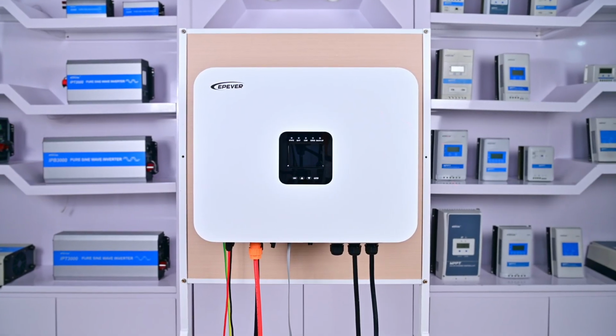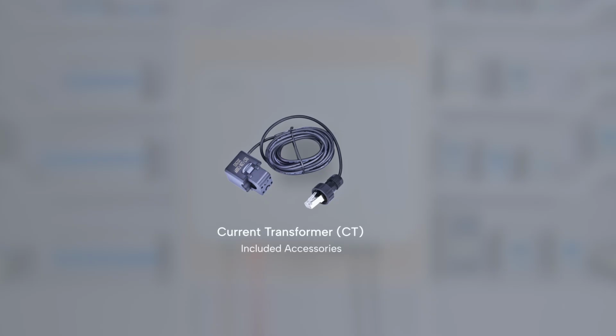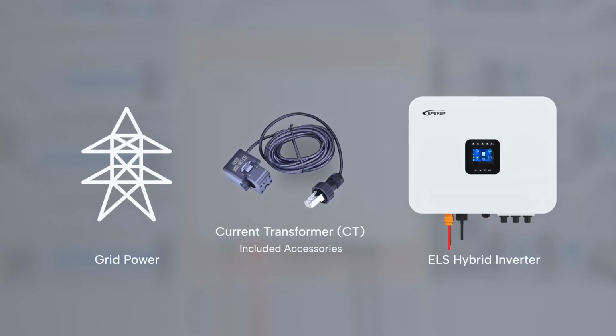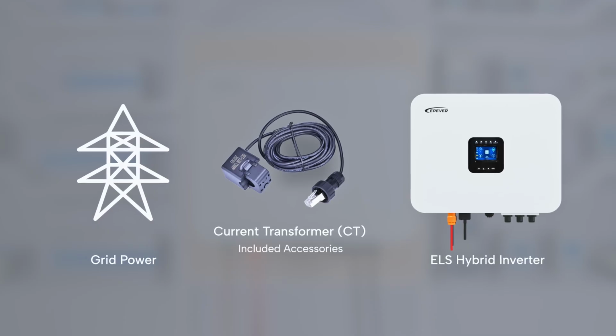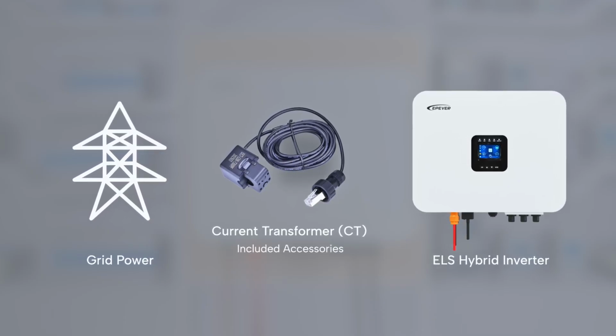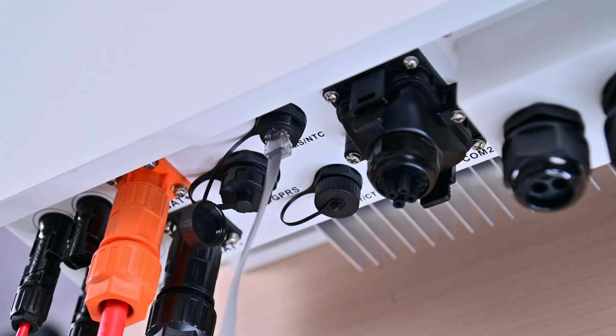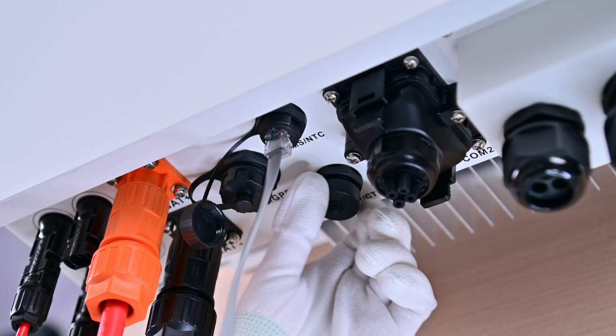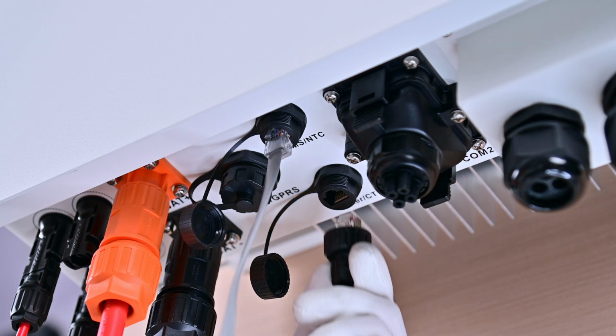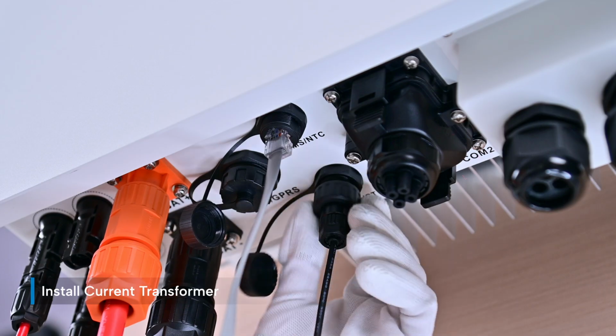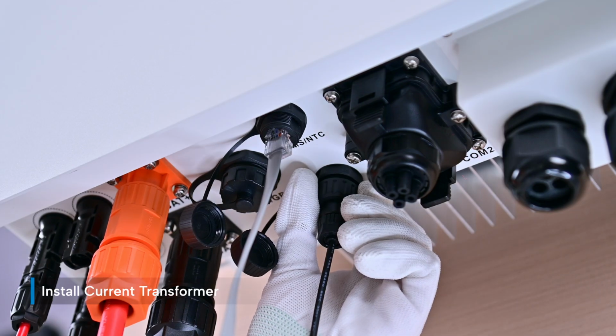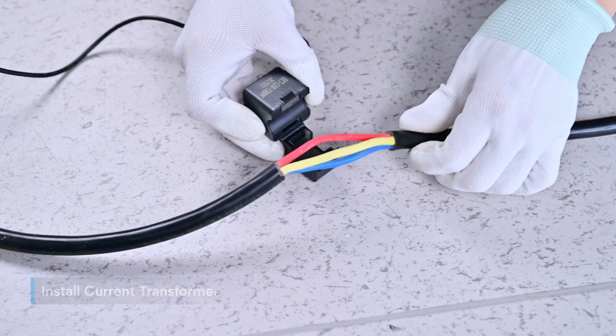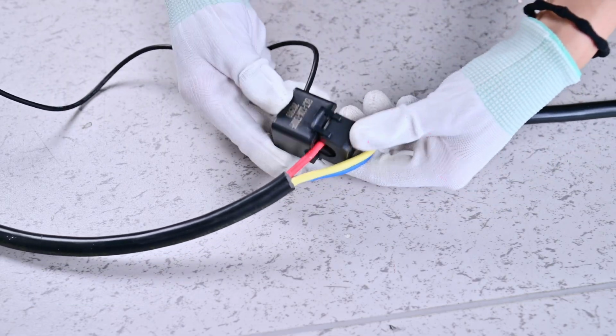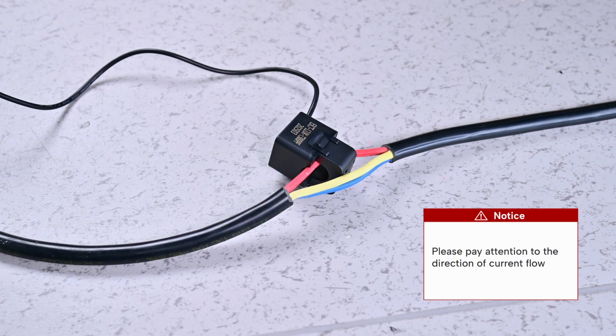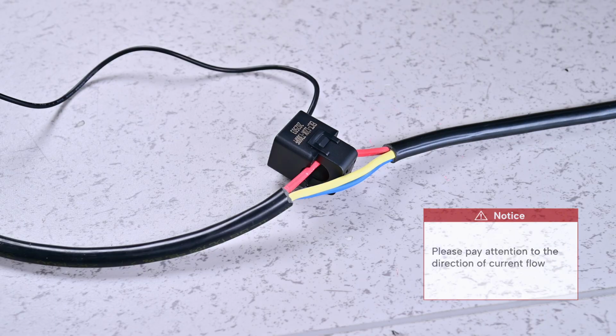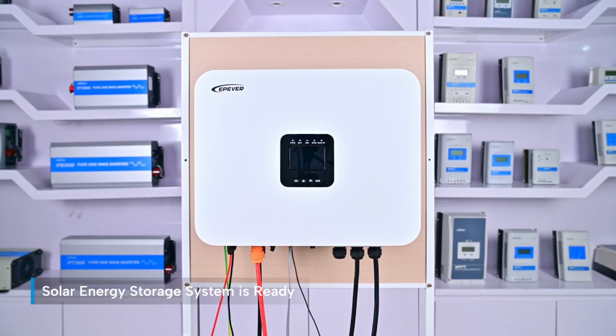Install current transformer. The current transformer, commonly referred to as a CT, is used to implement backflow protection. You need to install it if you want to precisely control the amount of power the device feeds back into the grid. Plug one end of the current transformer communication cable into the meter CT port on the ELS. Then connect the other end to the utility power cable. Note: please pay attention to the direction of current flow. The solar energy storage system is ready.